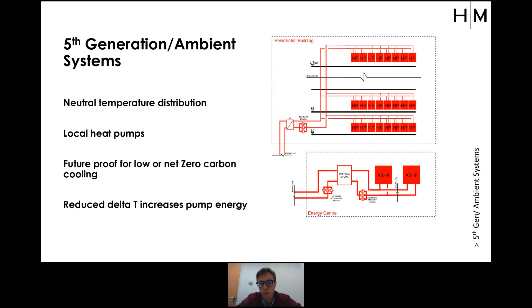The other great benefit to these is that they run at neutral temperatures, so your waste heat losses are almost negligible, and you can then look at waste energy that's far lower in temperature. So that opens the window for many different types of heat recovery, and also recovering waste heat from the actual network itself. So having local heat pumps, and I didn't really go into this, it's very similar to a conventional energy network, be it central air source heat pumps, or these could work with other heat sources, and then you have local heat pumps that step it up.